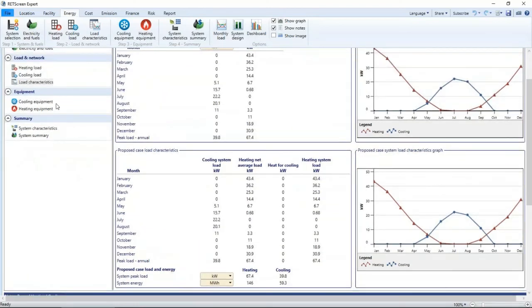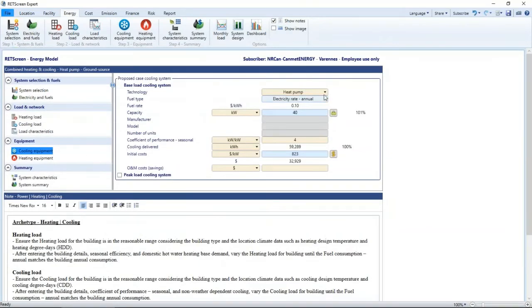In step 3, cooling equipment form, heat pump is first selected using the drop-down list. The capacity has been set equal to the peak cooling load, in this case 40 kilowatt. This value could be converted to ton of refrigeration using the unit switch. The seasonal coefficient of performance is then entered. The cooling energy delivered by the heat pump is calculated. Since the capacity of the heat pump was designed to meet the peak cooling load, the cooling delivered is also meeting the cooling energy required.